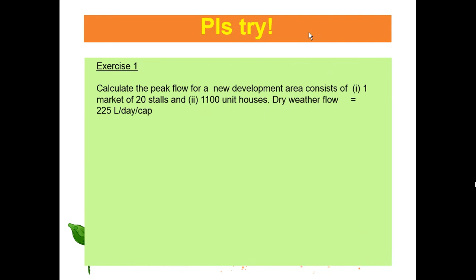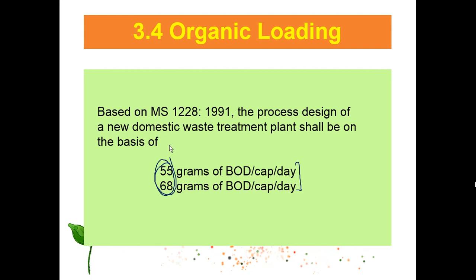So here, based on the Malaysian Standard MS 1228, the process design for a new domestic wastewater plant should be on the basis of 55 grams of BOD per capita per day. So between this range, 55 to 68 grams of BOD per capita per day. Okay, so we proceed for the process.